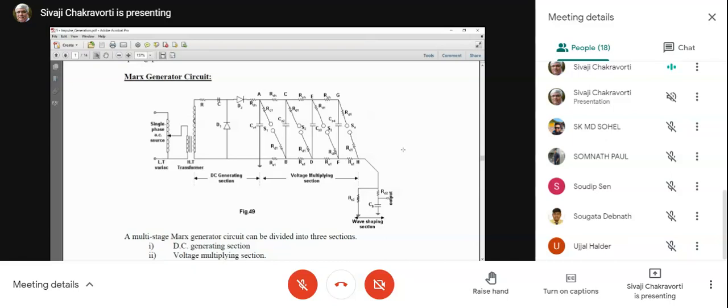At this condition, we have to fire this surge generator, and we have to fire it in such a way that their voltages should be added. That means these capacitors must be connected in series. Now what happens? By some means, which I will explain, this is called triggering of the generator. This first S1 gap is fired.